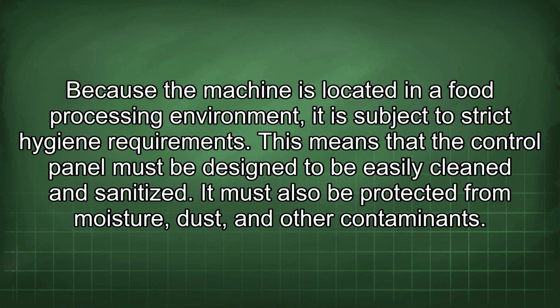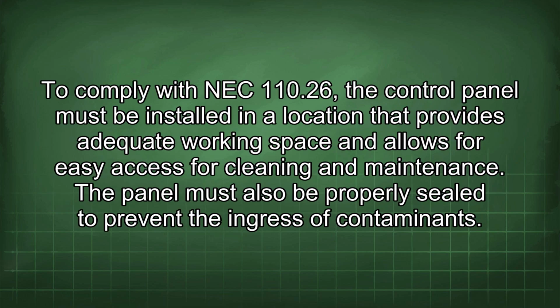Because the machine is located in a food processing environment, it is subject to strict hygiene requirements. This means that the control panel must be designed to be easily cleaned and sanitized. It must also be protected from moisture, dust, and other contaminants. To comply with NEC 110.26, the control panel must be installed in a location that provides adequate working space and allows for easy access for cleaning and maintenance. The panel must also be properly sealed to prevent the ingress of contaminants.